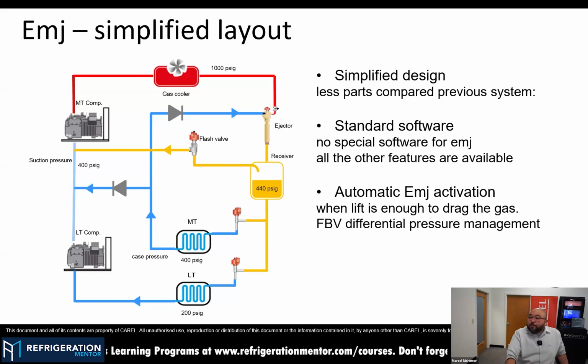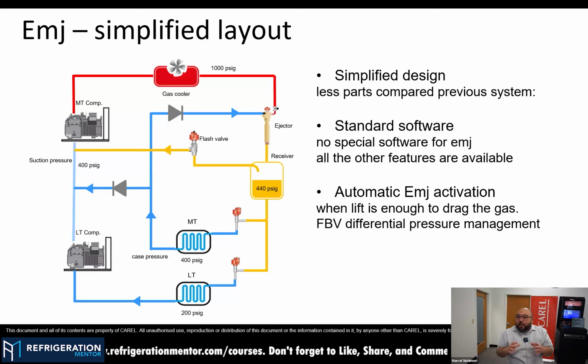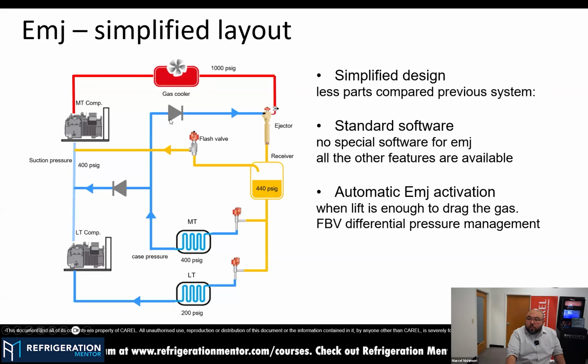Let me just come back here. And so another positive effect with using the CAREL ejector is that everything is done seamlessly. So you don't need to go there and change a parameter to make it ejector mode or traditional booster rack mode. It will be done according to the external conditions, and the system will be adjusting by its own. So when the ejector can be working, it will work because I just have mechanical components, check valves here. So less failure points, less wiring to check during troubleshooting. And everything here is basically thermodynamically done. So it will operate to one side or the other in a simplistic way.